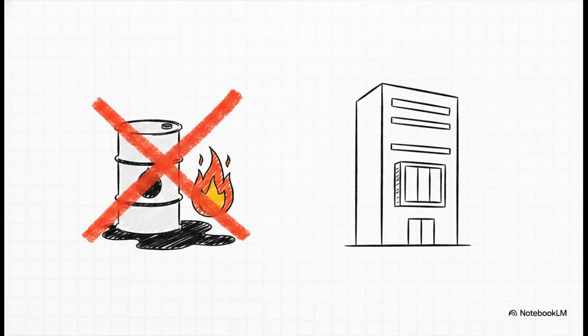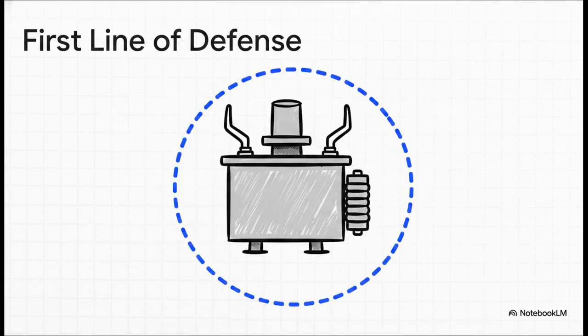Well, the answer comes down to strict environmental safety. Oil is inherently flammable, and if a tank ruptures or leaks, it is incredibly messy and hazardous. Think about it. When you're placing a transformer inside a hospital or a commercial basement, having hundreds of gallons of flammable oil sitting in a steel box is a risk that simply cannot be tolerated. You absolutely do not want a massive indoor oil slick next to an emergency room generator. So engineers specify dry type for transformers for indoor use. Sure, you trade away a little bit of cooling performance, but in return, you completely eliminate that fire and spill risk from the building. So the crucial point is this.